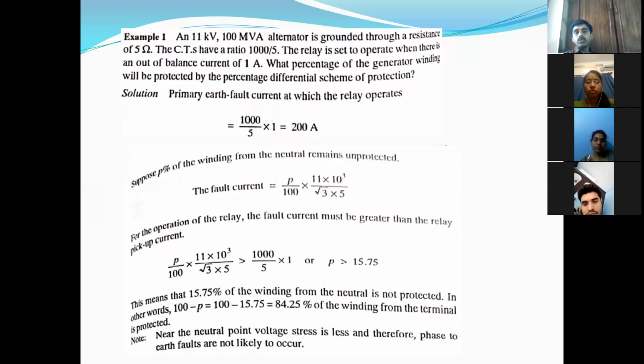So the fault current is equal to P into 11 into 10 cube, 11 kV divided by root 3, because we have to take the phase voltage, since 11 kV is the line voltage, divided by R, divided by 100. That is the fault current. Now, what is the primary earth fault current at which the relay operates? Because 1 ampere is the CT secondary current, 1 into the CT ratio is the primary current, 200 amperes.